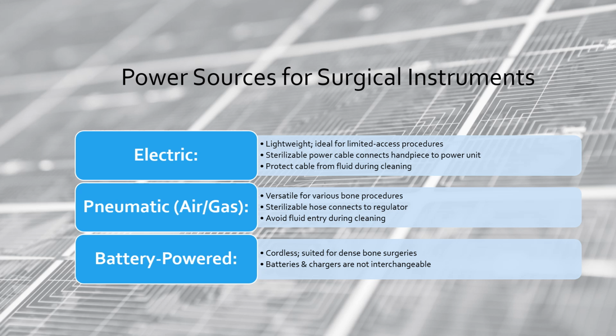Your pneumatic tools use either compressed air or compressed gas and are suitable for a wide range of the bones. Just like the electric systems, they require a sterilizable hose and must be cleaned carefully to prevent fluid from entering the hose. Battery power tools often offer the advantage of being cordless, so there's no cords involved, making them ideal for procedures on large, dense bones. It's important to note that their batteries and chargers are not interchangeable with different models.